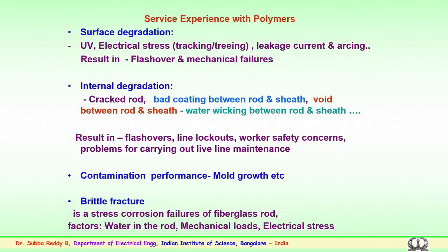Arcing could be surface arcing, what we call scintillations or partial arcs. This could be due to the formation of dry bands and wet bands on the surface, because the surface may not be continuously wet. These small bands, which form due to rain or fog conditions, where the surface becomes partially wet and partially dry, result in arcing known as partial arcs or scintillations. This depends on the surface conditions and the surface resistance offered. This dry band and wet band formation, followed by leakage current, could lead to flashover, and sometimes mechanical failure because of fiberglass rod failures. There could be a mechanical failure where the line could get detached.